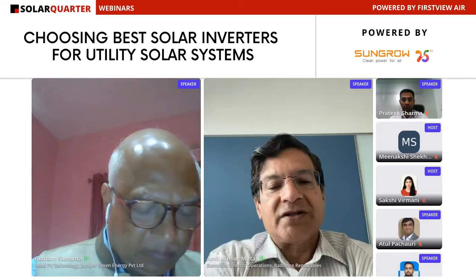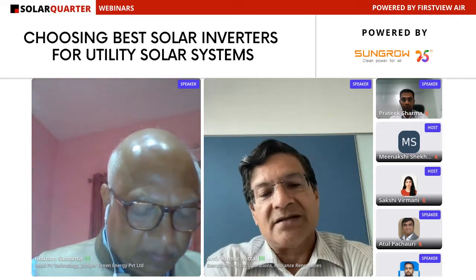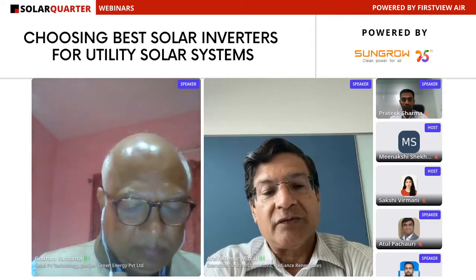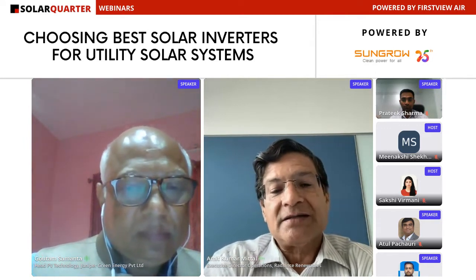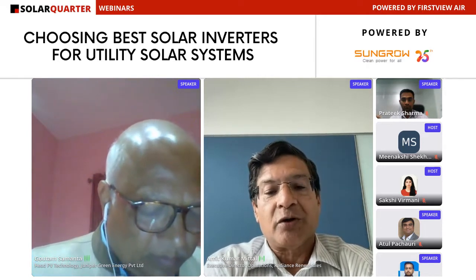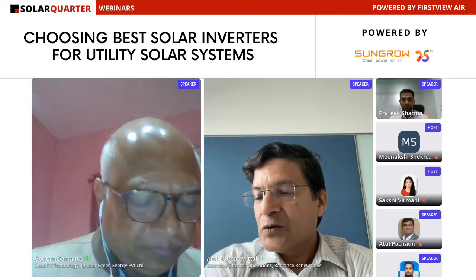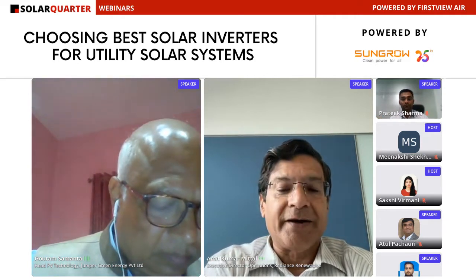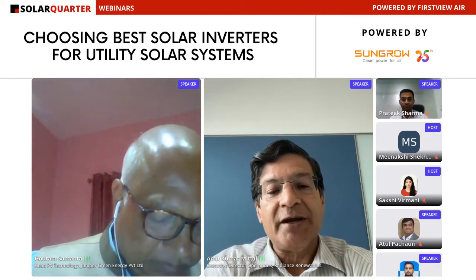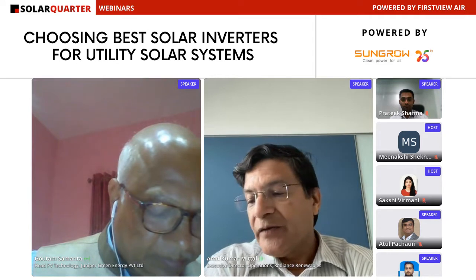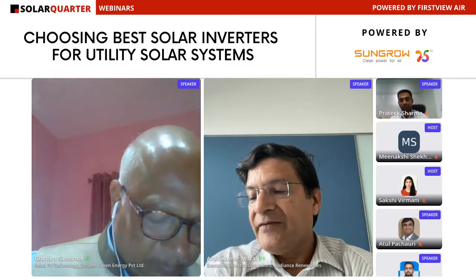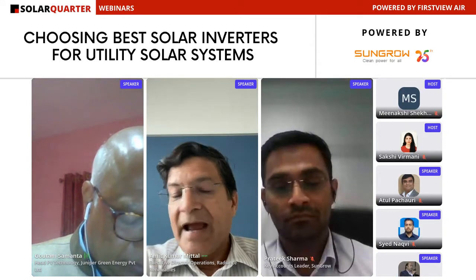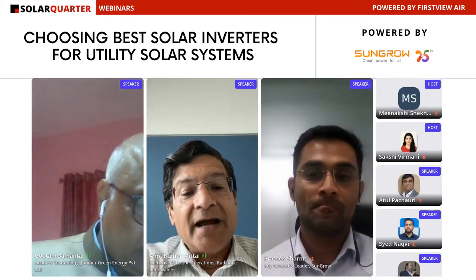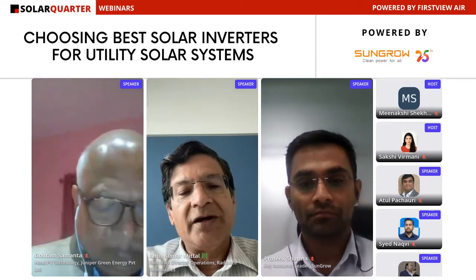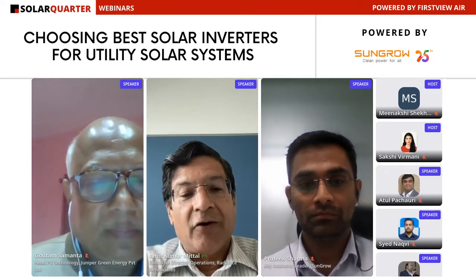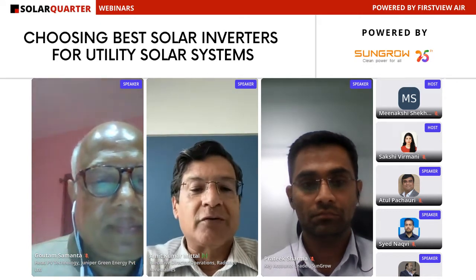Overall, there's been a lot of improvement in both central and string inverters in terms of technology upgrades and increasing inverter size, making them more competitive on an LCOE basis. There's also been a lot of support for grid stability as more renewable energy is pumped into the grid. Grid support features like LVRT, HVRT functionality, anti-islanding facilities, and nighttime reactive power compensation are now default features that help improve overall system design.